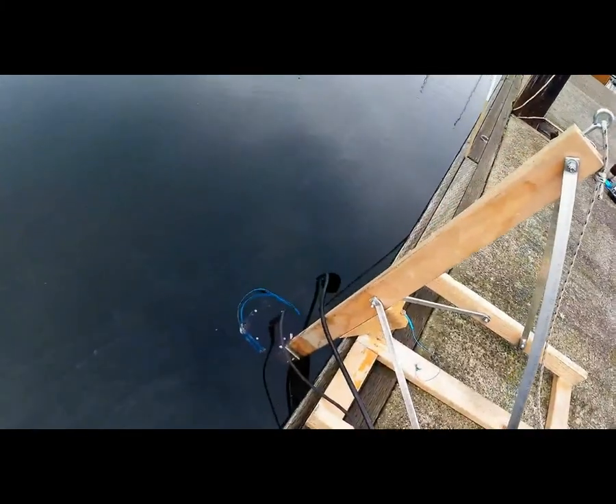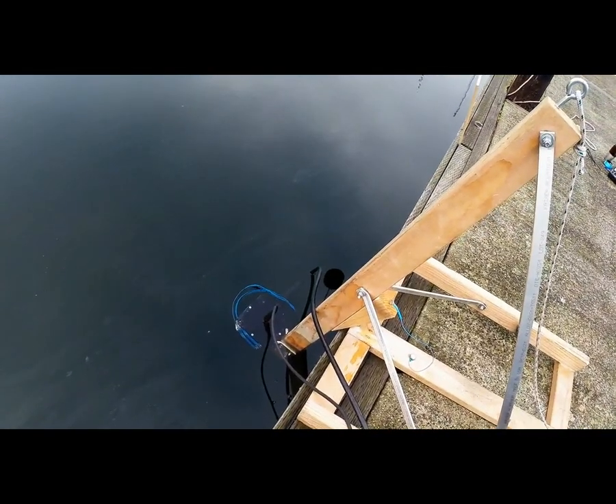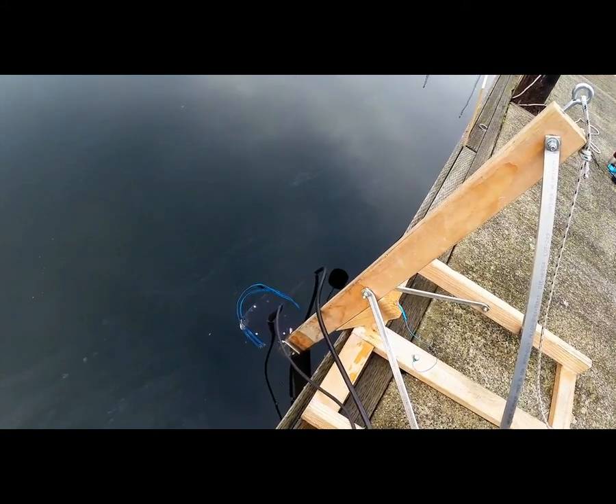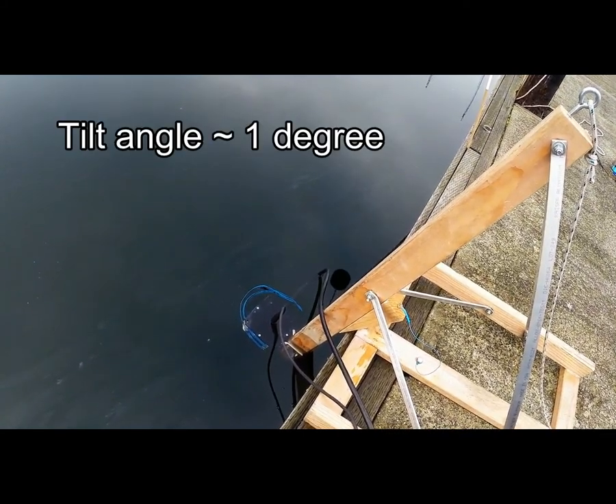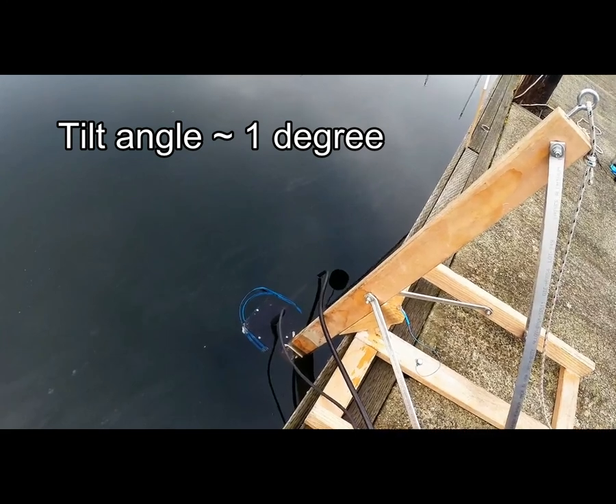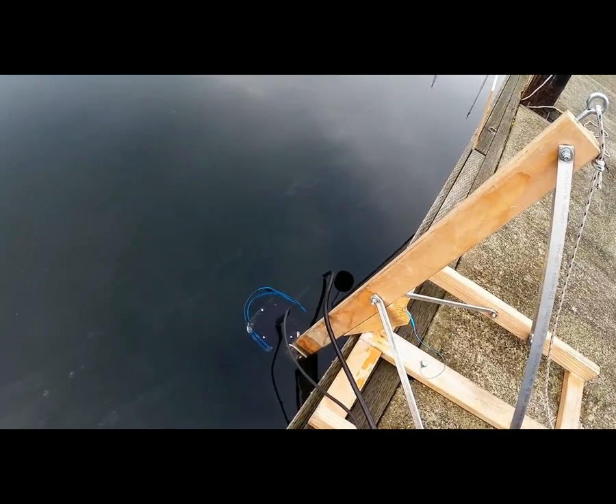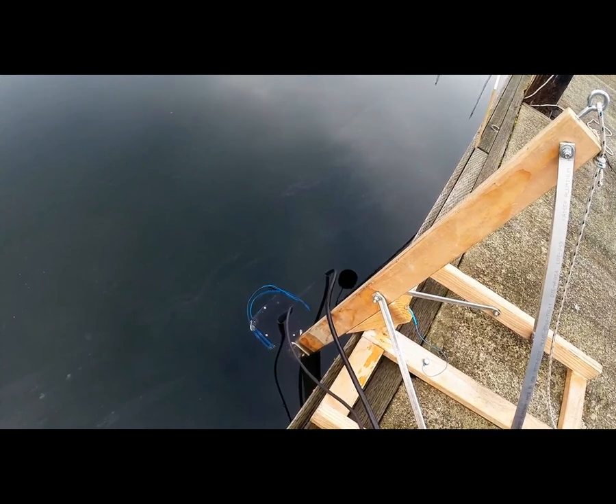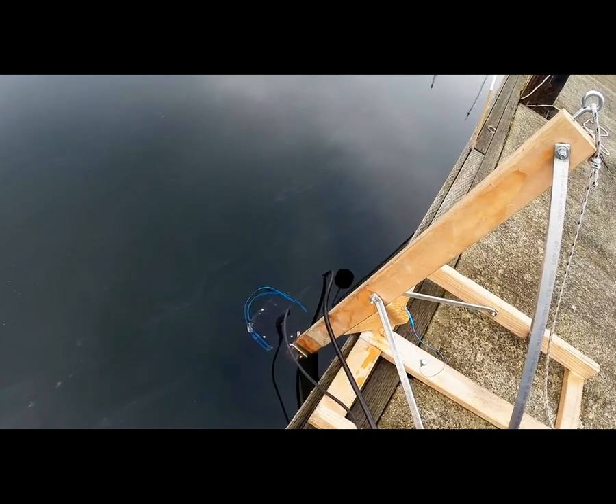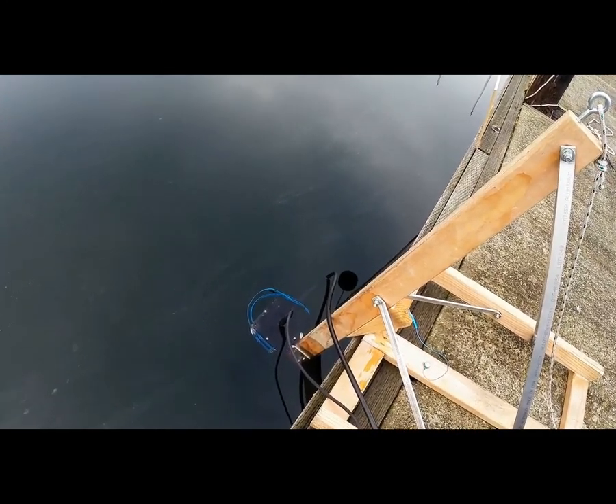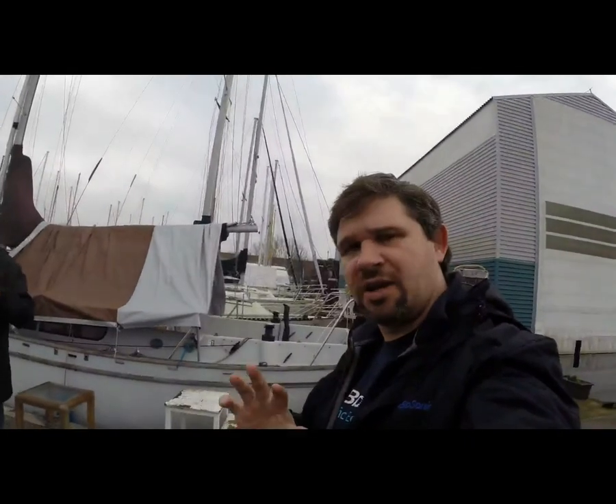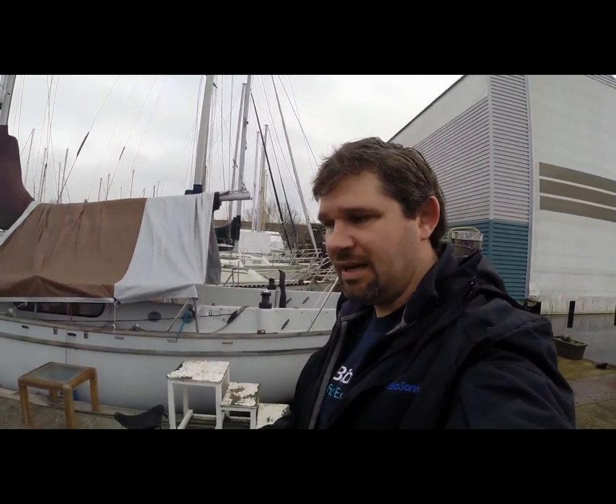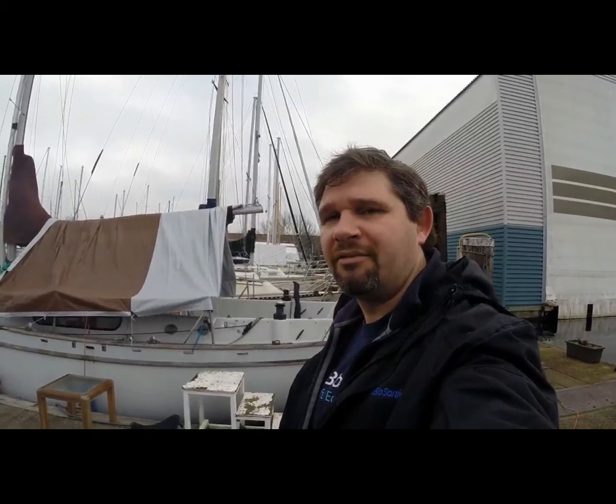It might be hard to see, but we do like to have the transducer slightly tilted away from us, or toward just a slight tilt, so it's easier for us to get the calibration sphere underneath the center, so you're not trying to swing your line into where it's impossible to get because of the transducer. It's important to make sure you get your calibration sphere in all the quadrants, so if you artificially can't get it to one side because of the way your transducer is placed, you might get a false indication that there's a problem.